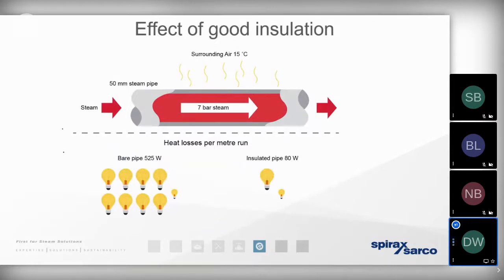So one of those calculators and configurators that we have on our website will help you understand the beneficial effect we can have by increasing the grade of insulation, by doing so, reducing the heat losses, and retaining as much steam in the distribution pipework as we possibly can. And those calculators can give an indication with regards to the payback that you can enjoy in financial terms simply by increasing the grade of insulation.